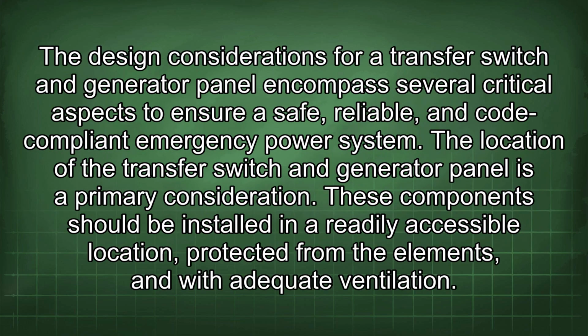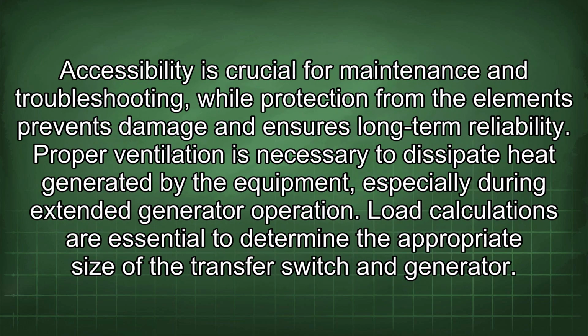The design considerations for transfer switch and generator panel encompass several critical aspects to ensure a safe, reliable, and code-compliant emergency power system. The location of the transfer switch and generator panel is a primary consideration. These components should be installed in a readily accessible location protected from the elements and with adequate ventilation. Accessibility is crucial for maintenance and troubleshooting, while protection from the elements prevents damage and ensures long-term reliability. Proper ventilation is necessary to dissipate heat generated by the equipment, especially during extended generator operation.